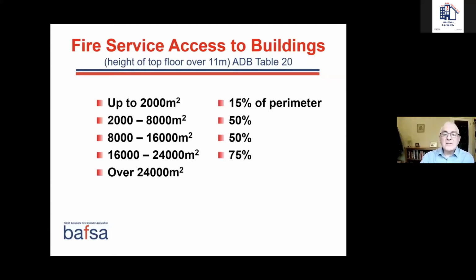So these are the figures in the approved document. Up to 2,000 square meters, we're only required to provide 15% of the perimeter for access for a fire appliance. But those are what we might call smaller buildings, and there are other rules in relation to how far away the appliance must be. Once we get into 2,000 to 8,000, we're starting to get into some decent sized buildings.